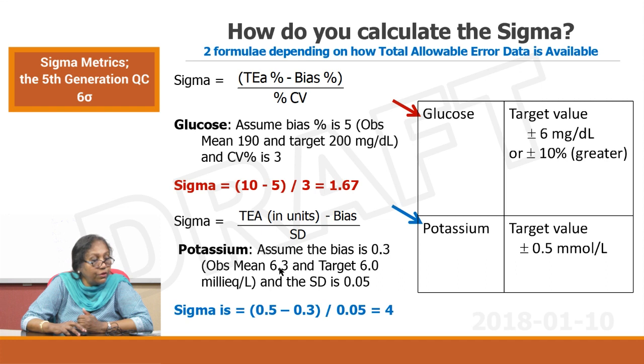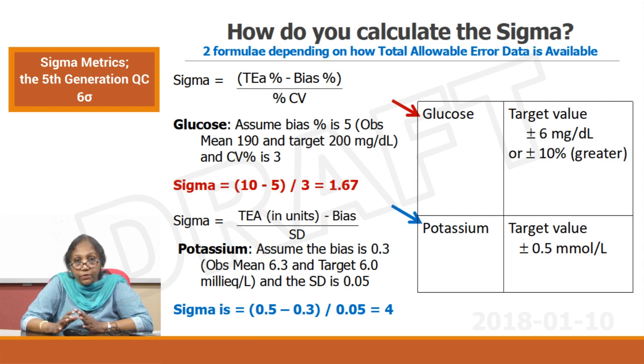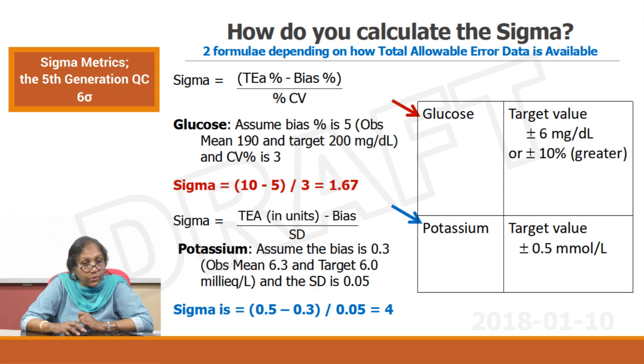Another example — in units for potassium: the potassium target value is plus or minus 0.5. Assume the bias is 0.3, the mean is 6.3, the target is 6. In the calculation you will see that you have got a 4 sigma performance, which is a good performance. You will say, oh that is good, maybe I can improve, but at this point I will not worry about my potassium performance. I might worry about my glucose performance. This is how you evaluate your performance by sigma and then setting your tolerance limits.